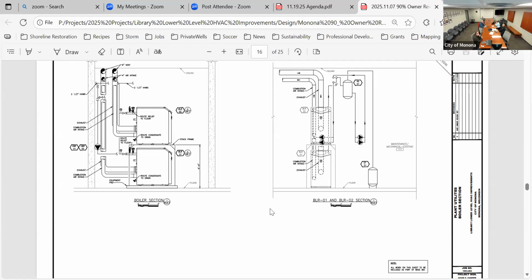We are putting a treatment system in for the boiler loop. The water here is extremely hard and partially acidic, or becomes acidic because it has iron in it, and it will eat rubber gaskets away over time. One of the problems with new pumps is that they're all rubber gasketed, and it's cheap. Everything's made cheaper, and they dissolve, and then we have leaks. Yeah, it's a pain in the butt.